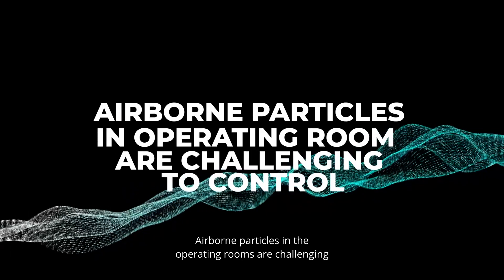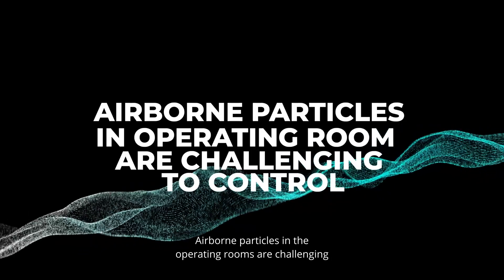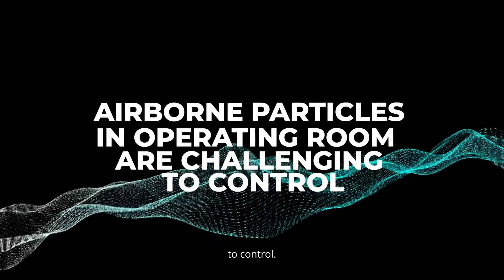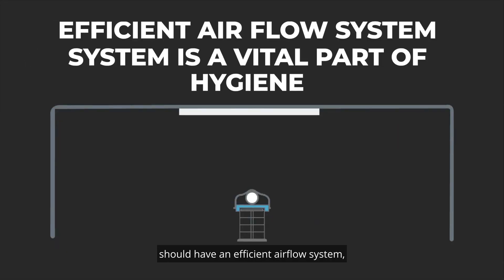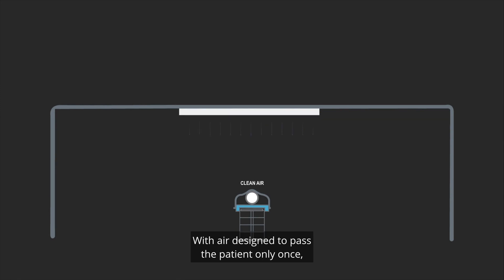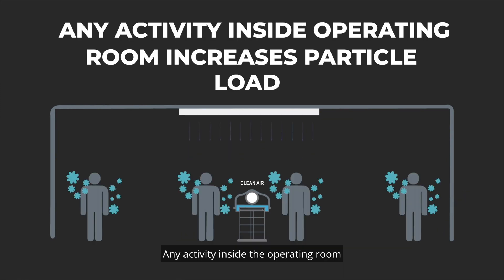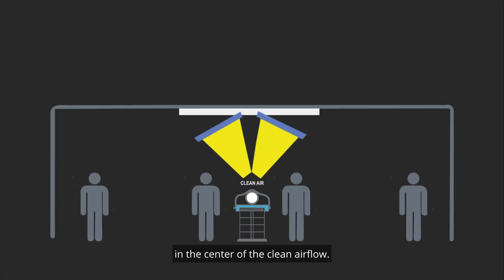Airborne particles in the operating room are challenging to control. Every operating room should have an efficient airflow system — it's a vital part of hygiene, with air designed to pass the patient only once. Any activity inside the operating room increases particle load, and surgical lights are placed in the center of the clean airflow.